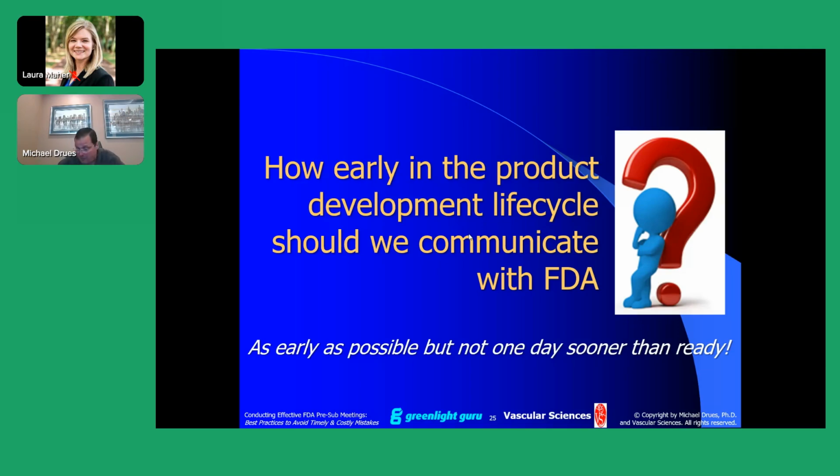One challenge, though: as I mentioned a moment ago, it's never too early to go to the FDA with a device, even if you just have a prototype. In some cases, I've taken devices to the FDA as a pre-sub where we don't even have a prototype yet, where it's just a concept. That does present challenges because, let's be honest, most FDA reviewers are not used to seeing or thinking about or talking about products that are not yet at design freeze and at the point of final submission, where every single question should be able to be answered. When you go early in the product development process, there are many questions that you probably can't answer yet, but that's okay. I still want to have that dialogue, that engagement with the agency as early as possible.